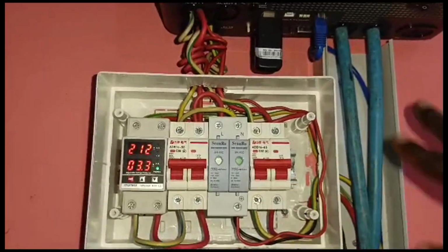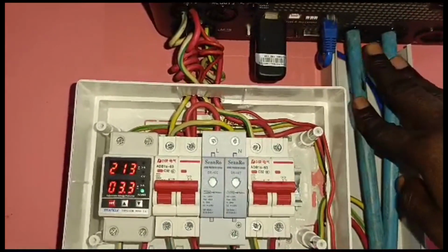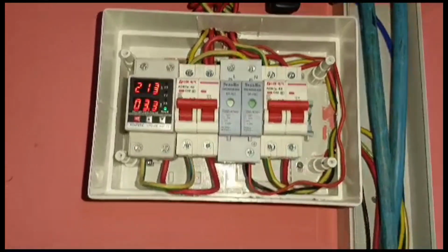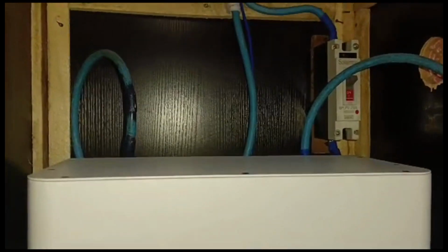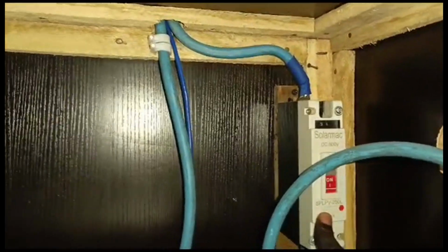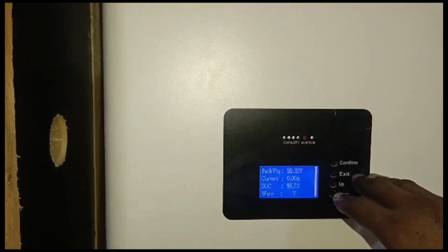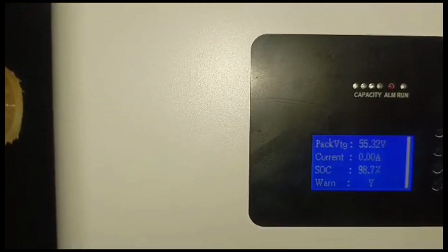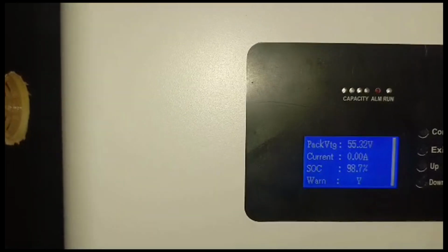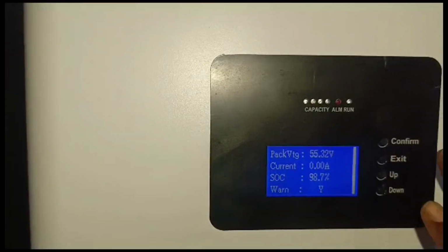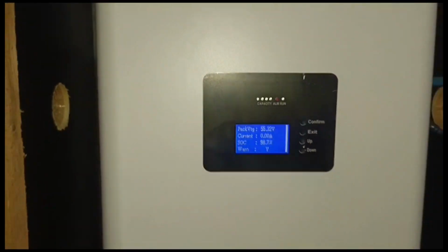And for the DC side, you have a 50 mm cable connecting the inverter down to our 14.3 kilowatt hour surplus battery pack. That's a lithium battery pack. You have a 250 amps breaker for the battery here. The battery is fully charged now, although it's not at 100%. Based on the setting, it stays at 98.7%, and there's a reason for that.